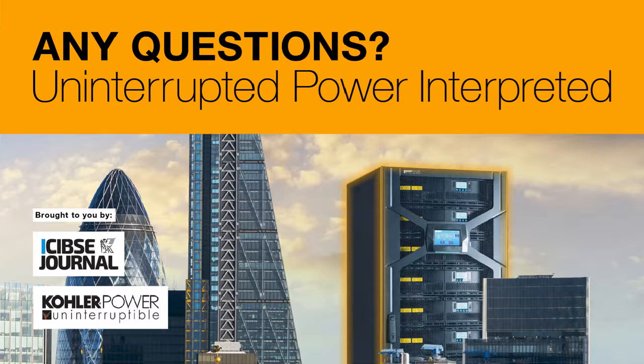A question from Carl here. How critical is battery conditioning when commissioning a UPS? And perhaps I can also add a question from Yuck, who's asking from Hong Kong. What's the purpose of the maintenance process? What does that do for the battery life? At commissioning, the batteries typically come out of the manufacturer's about 90% charged or so. However, they need to be on charge for 5 to 7 days before you do anything, to allow them to equalize out. We can, and sometimes get asked to, do a load test on those batteries, and that is purely to prove the calculation that the battery and everything supplied is as designed. It's not a necessary thing for the battery. The batteries have already been tested at the manufacturer's, so that's not required.